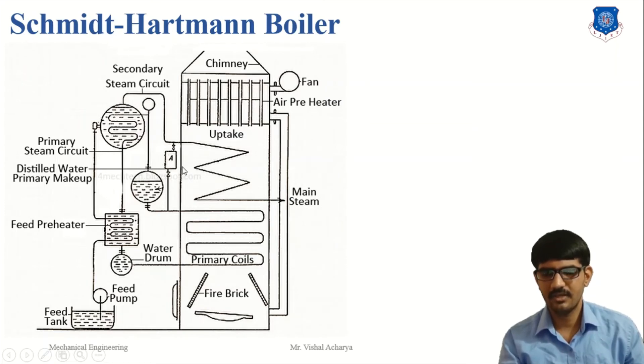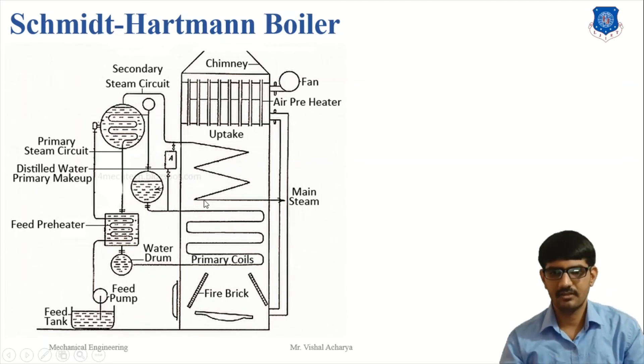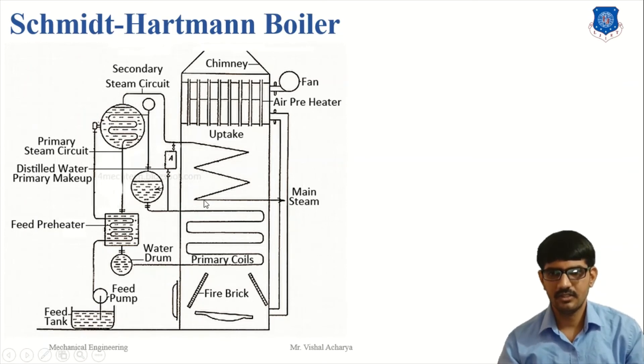This is the working of the Schmidt-Hartmann boiler. The main devices are the feed pump, evaporator coil, steam separator, steam generator, and feed preheater. Air is transferred from the air preheater to the furnace. This is a two-circuit boiler where the overheating problem and salting and corrosion problem in the tubes are solved by the two circuits. The first circuit uses distilled water and the second circuit uses impure water.